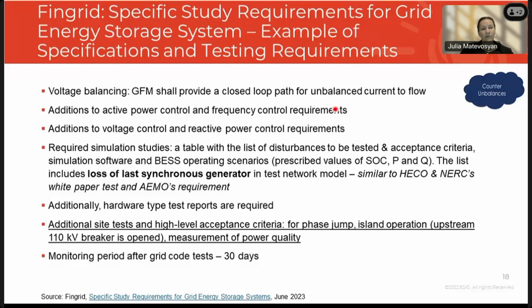There are different battery storage operating scenarios that are described. There is a prescribed state of charge from which you start testing, and then different P and Q output conditions pre-disturbance. The list also includes this loss of last synchronous generator test that I mentioned is also present in HECO's requirement, the NERC paper, and in the AEMO requirement. And additionally, they require hardware type test reports.